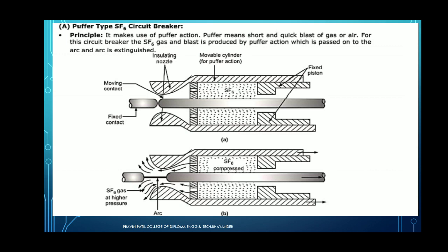This is the diagram representation of the SF6 circuit breaker. It makes use of the puffer action, meaning a short and quick blast of gas or air takes place. For this circuit breaker, the SF6 gas blast is produced by puffer action, which passes on the arc, and then the arc gets extinguished.